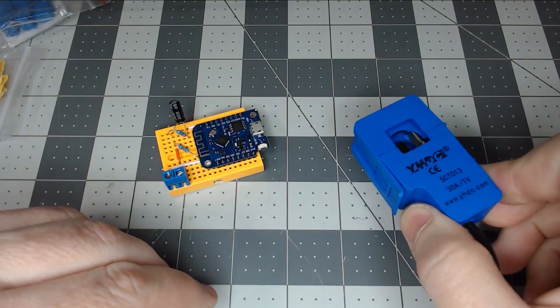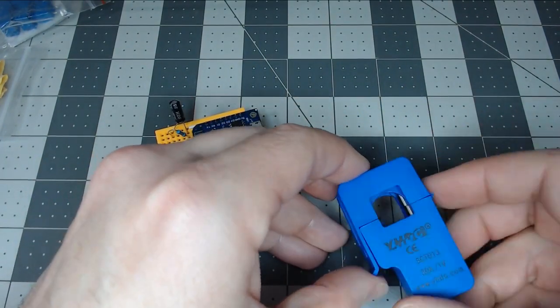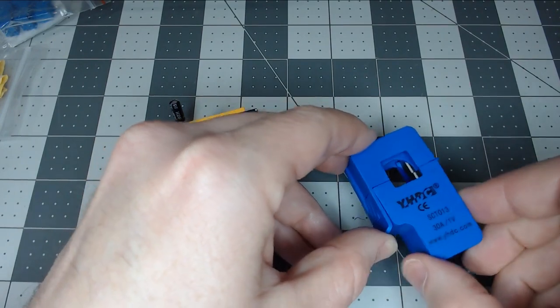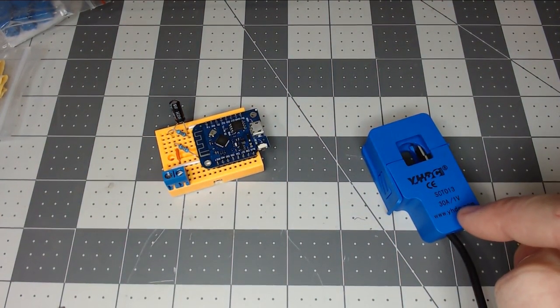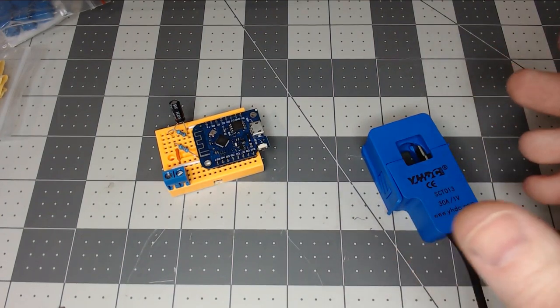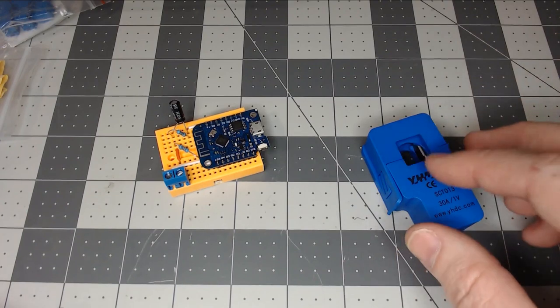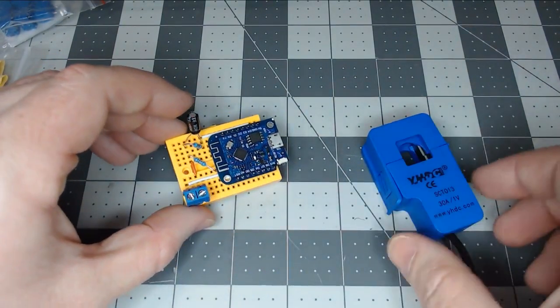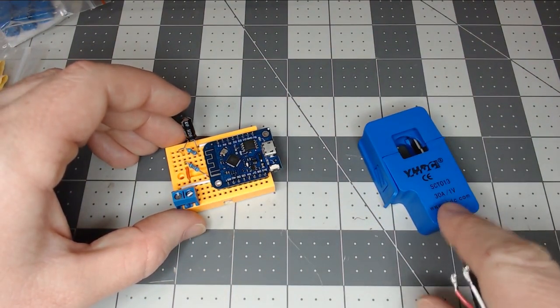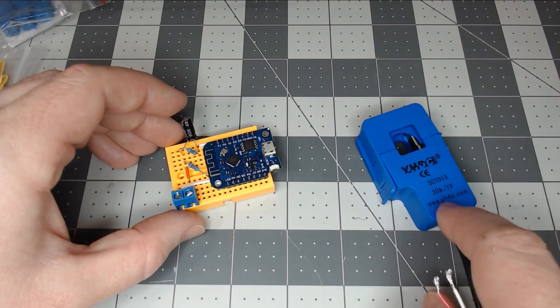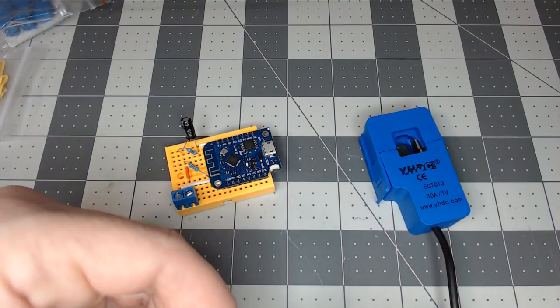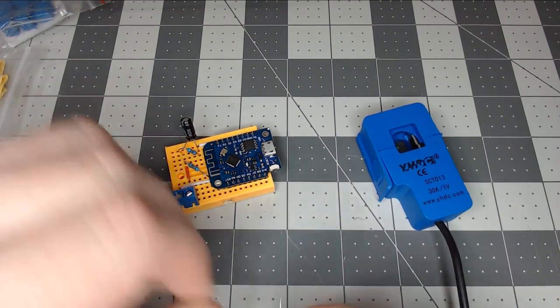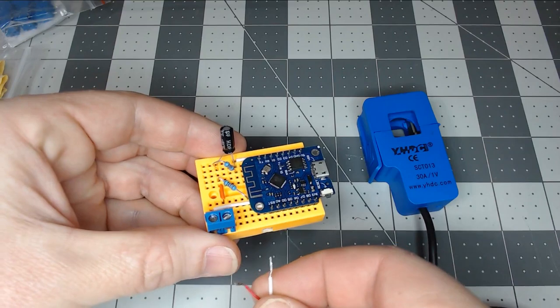So there are several of these type of split-core current transformers. This one we're using is a 30 amp 1 volt output. There is what they call a burden resistor built into the unit itself, which makes it a little bit safer given if you unplug it with the current being drawn through it. And also you don't have to put a burden resistor on your breakout board.